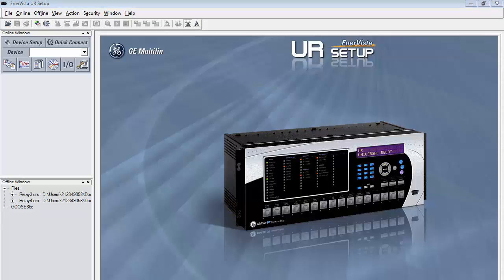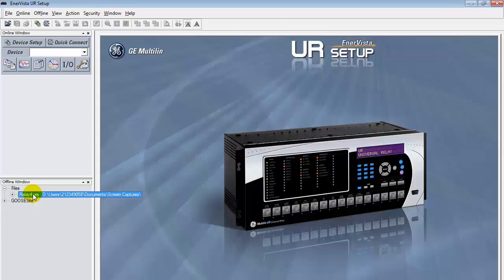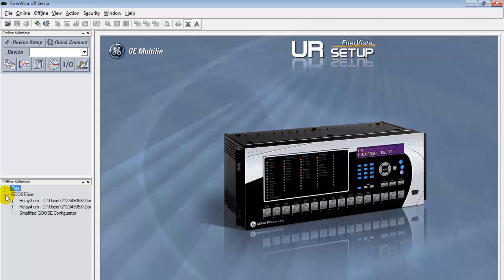The next step is to configure the GOOSE site for both UR relays. To do that, drag each offline file onto the GOOSE site. Now, open the simplified GOOSE Configurator.